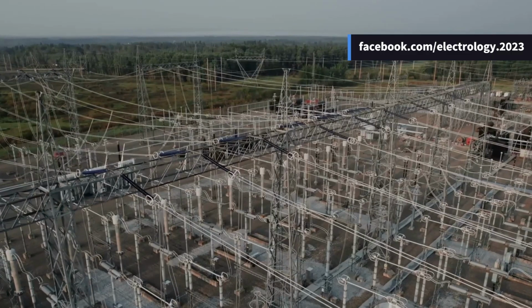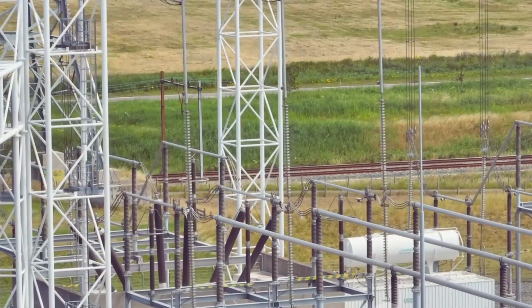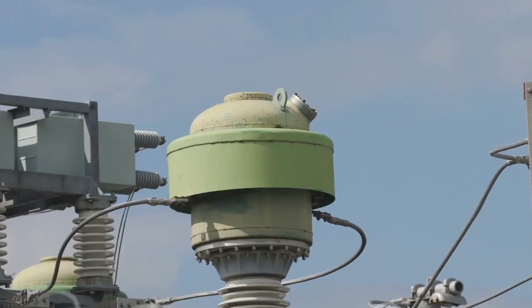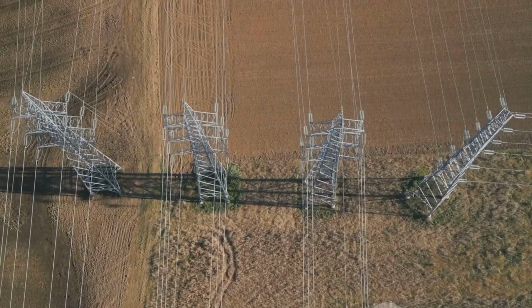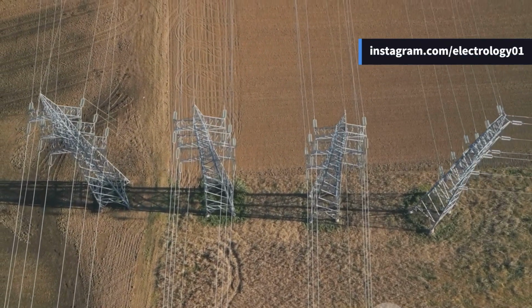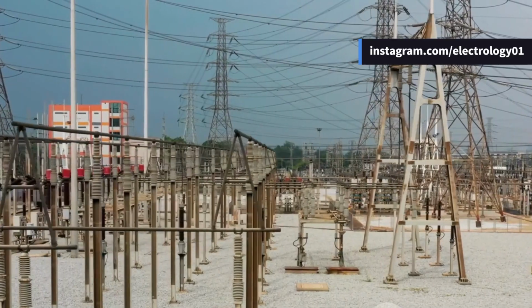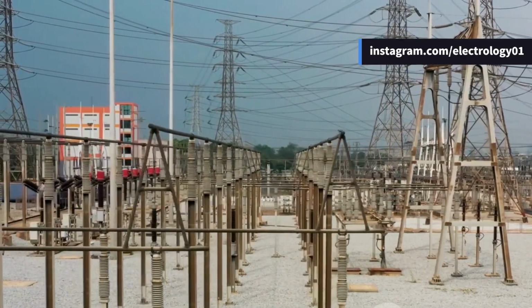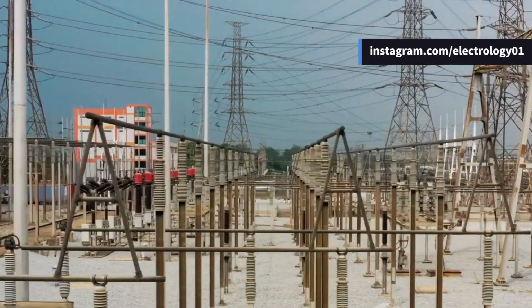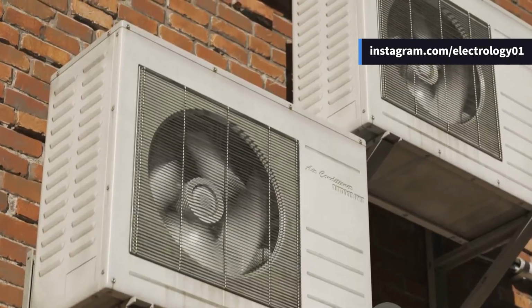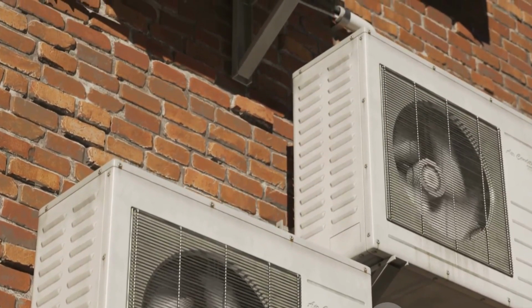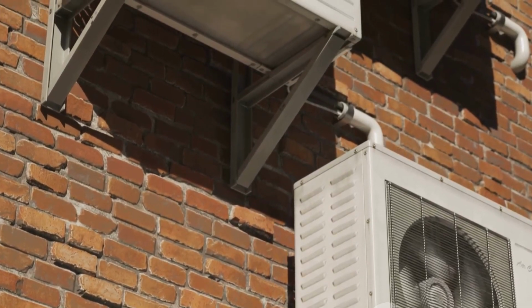Now, where are STATCOM devices used? They are widely used in distribution systems, and they provide several advantages. They improve steady-state loadability of transmission lines. Voltage rise caused by capacitor switching gets substantially reduced both in magnitude and duration. Voltage variations due to customer loading are also reduced significantly.